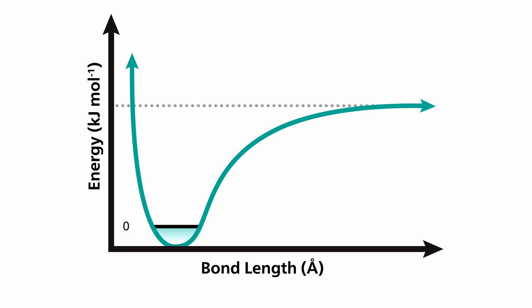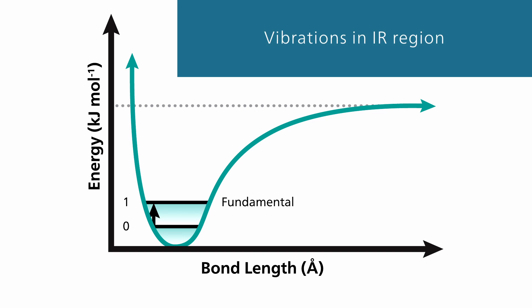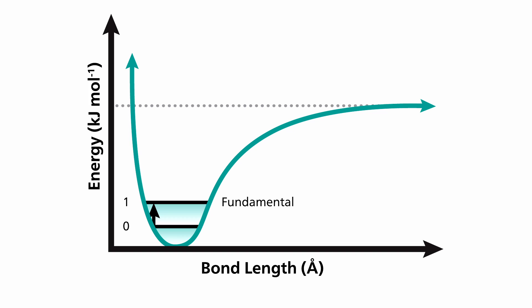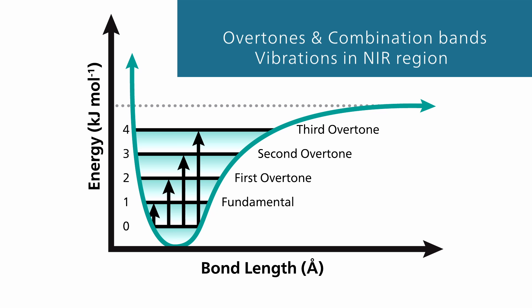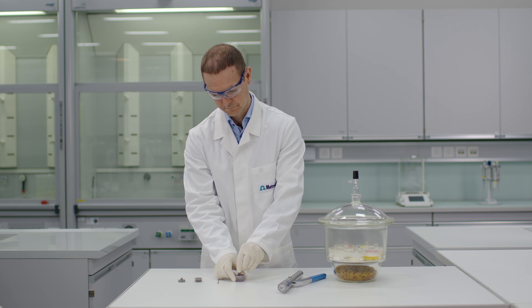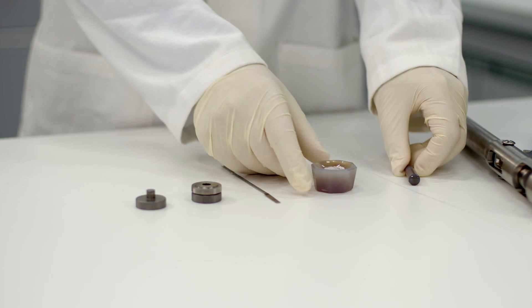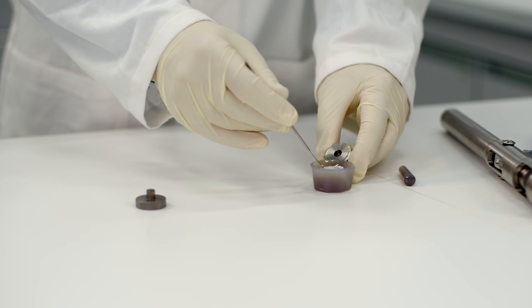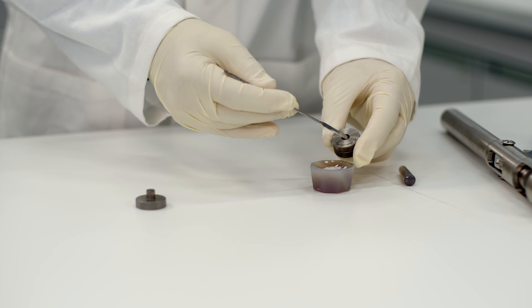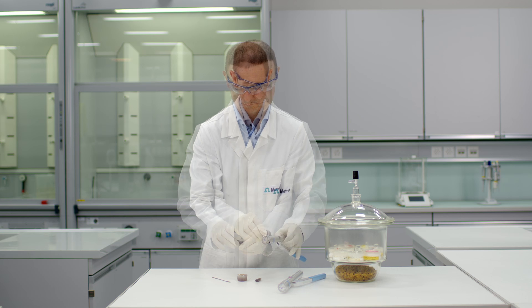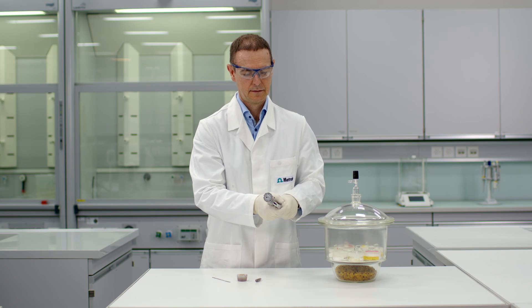Let's look at the first difference: the sample size. Vibrations in the infrared region are classified as fundamental vibrations. As such, they have a higher probability of occurrence than overtones and combination bands, which are vibrations happening in the near-infrared region. Therefore, infrared light is absorbed more strongly than NIR light. Because of this, small sample quantities should be used with IR spectroscopy. Sample preparation is often required as well, for example, needing to press a potassium bromide tablet or prepare liquid dilutions.